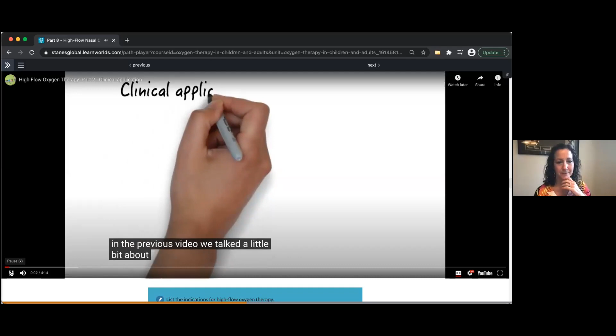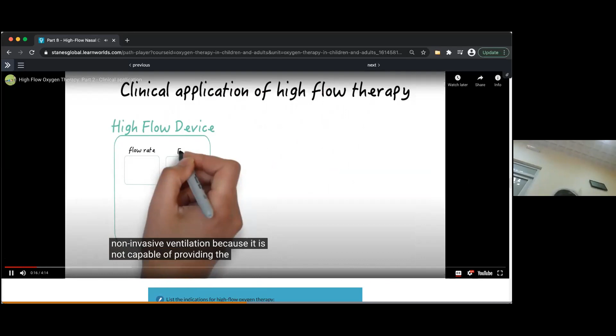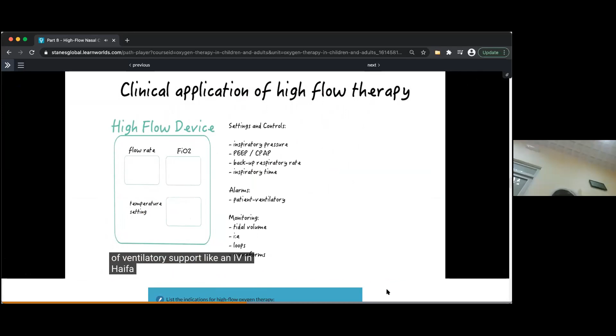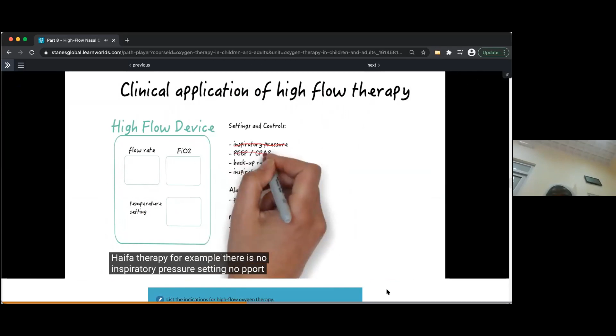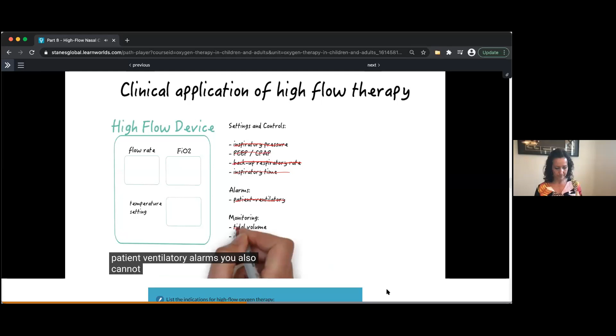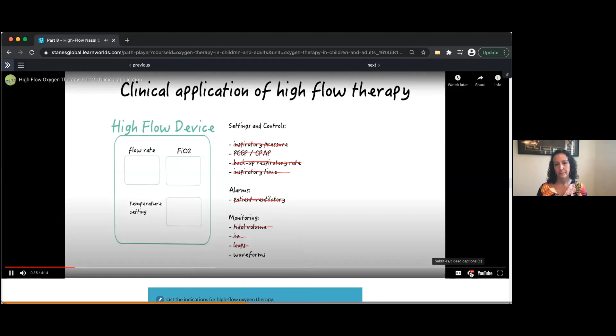In the previous video, we talked a little bit about what high flow therapy is. In this video, we'll quickly highlight the clinical application of high flow oxygen therapy. We already discussed that high flow therapy is not a replacement for non-invasive ventilation because it is not capable of providing the same level of support like NIV. In high flow therapy, there is no PEEP or CPAP setting, no backup respiratory rate setting, no inspiratory time setting, no patient ventilatory alarms. You also cannot monitor the tidal volume, the IE ratio, and there are no loops or waveforms. You get the idea. NIV, on the other hand, can provide all of these. In fact, the only 2 main controls on high flow therapy are FiO2 and flow.